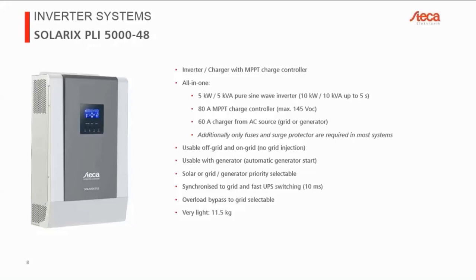Then we have the big brother, which has exactly the same functionality, so I think I don't need to explain it all again. The differences are, of course, the values, the power ratings. We have a 5 kilowatt inverter in this version. It's a 48 volt model for 48 volt batteries. And we can deliver 10 kilowatts for up to 5 seconds.